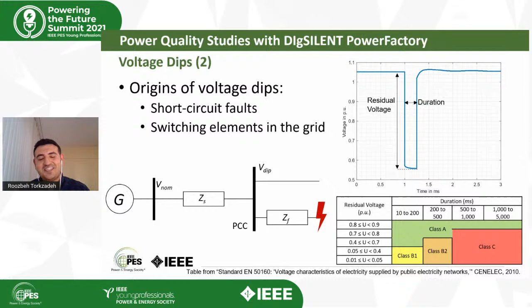Standards provide tables to classify the voltage dips based on their characteristics. For example, here I put a table from the EN 50160 standard. In this standard, 4 classes have been introduced, in which class A is an unharmful class, and if a dip happens in that class, the customer can prevent the consequences by spending a reasonable price. So the voltage dips within class A are not important, but for other classes B1, B2, and C, it's important to limit the number of those voltage dips. And this is where grid codes define precise measures and also precise limits, so for each voltage dip, for each client at each network, there should be a limit. And if that limit is exceeded, we need to investigate the origins.